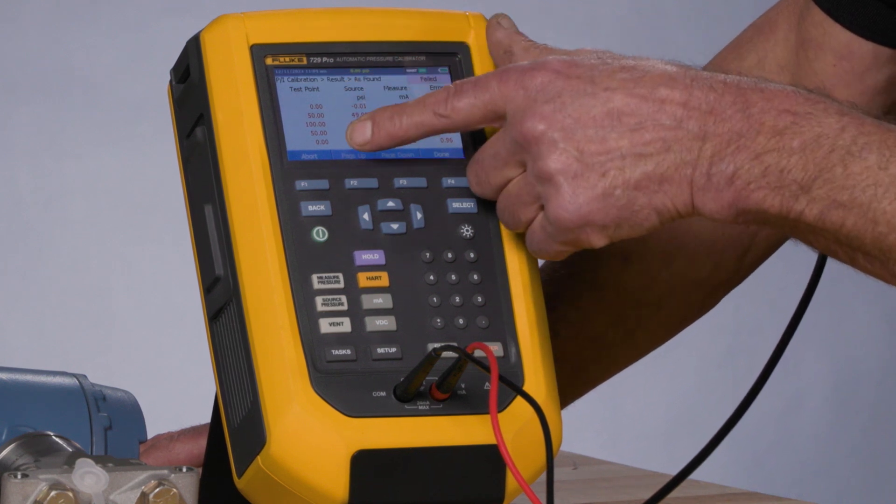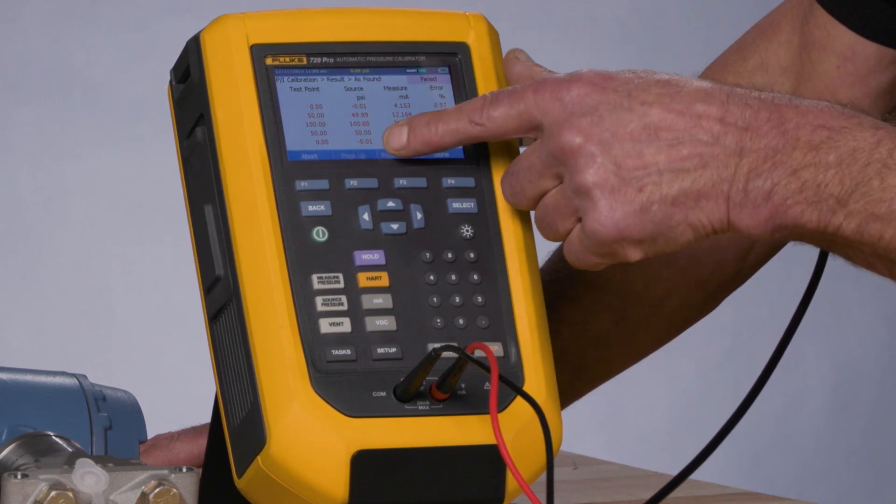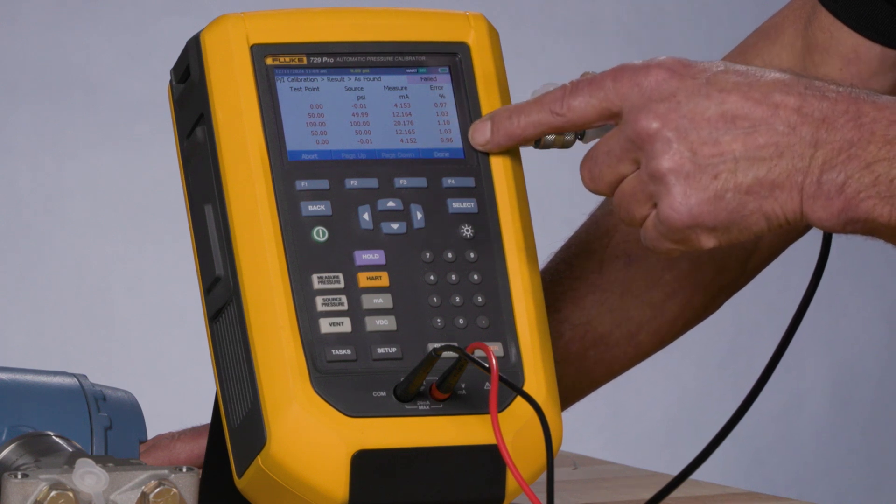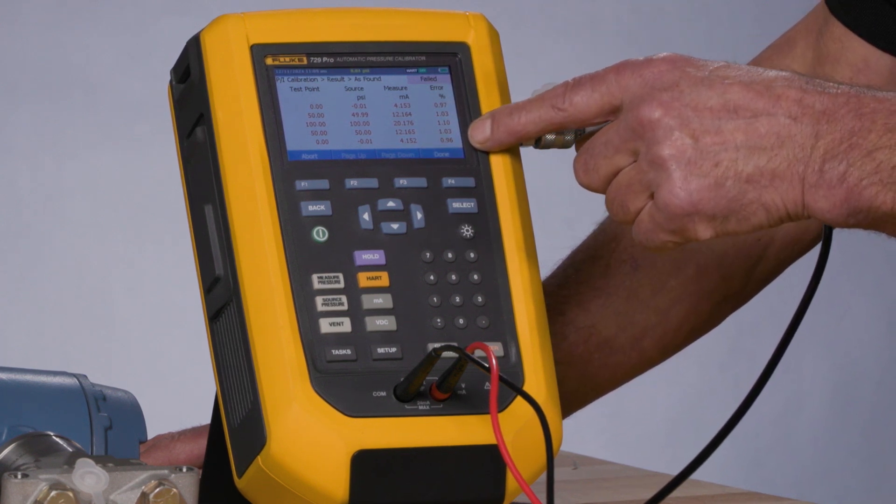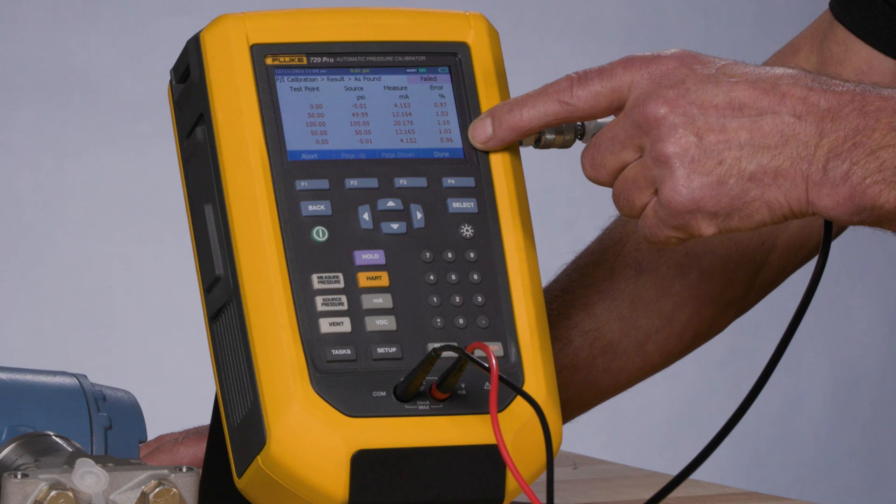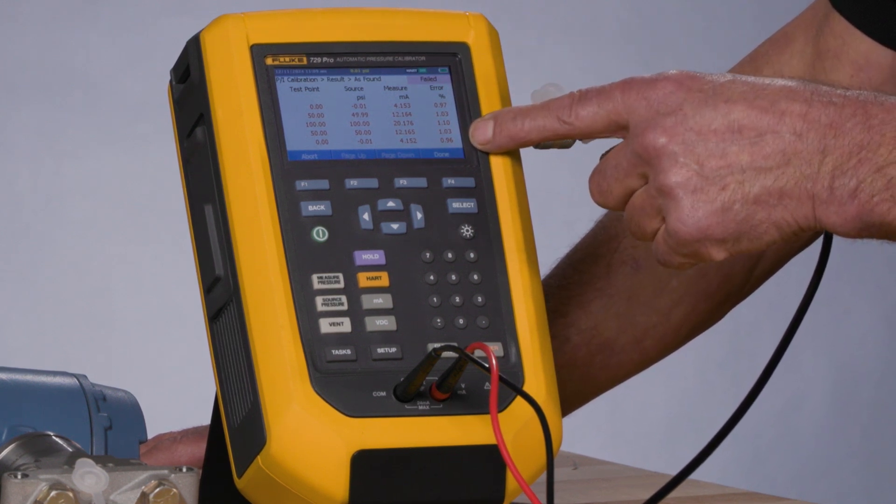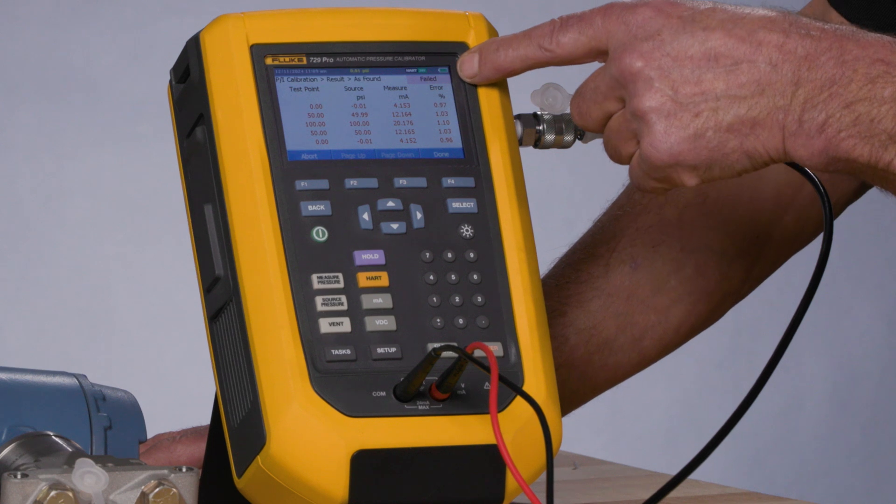So here's our post-test summary. Here's the ideal test point pressure, the actual applied pressure, the milliamp value that was measured, and the milliamp error percent is shown. Now since we had a 0.2% test tolerance typed in for our test, all of these errors are out of that particular test tolerance, and this is showing as a failed-as-found test.